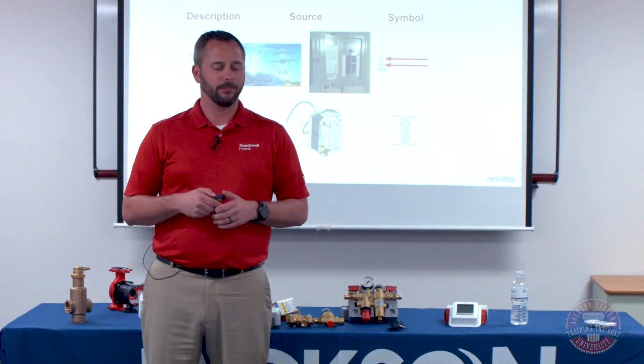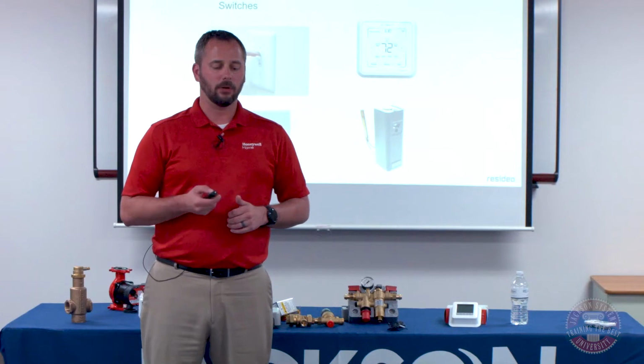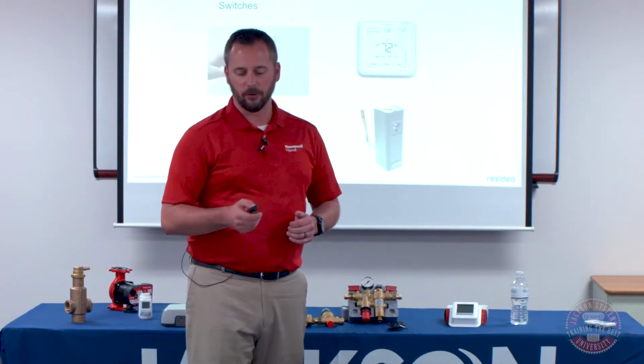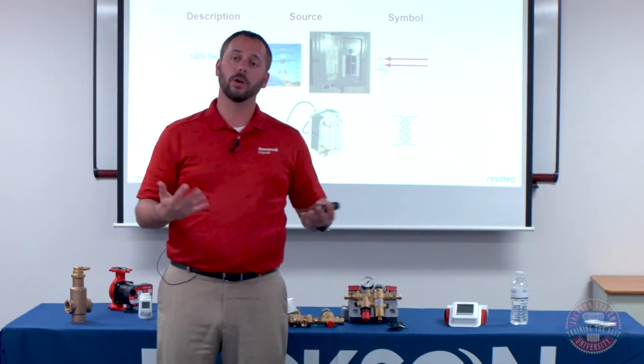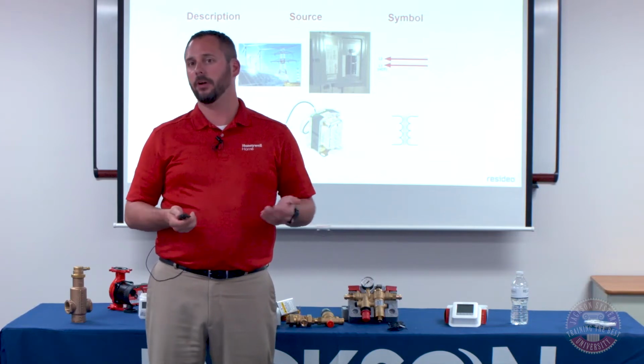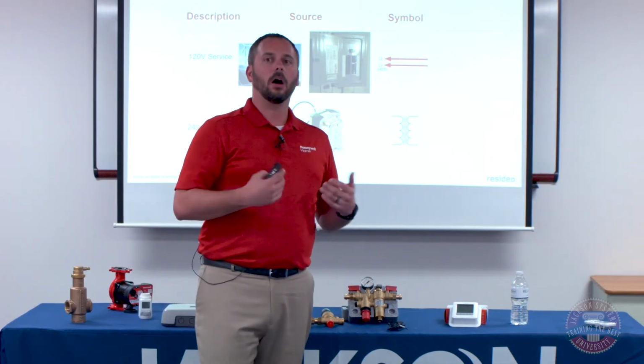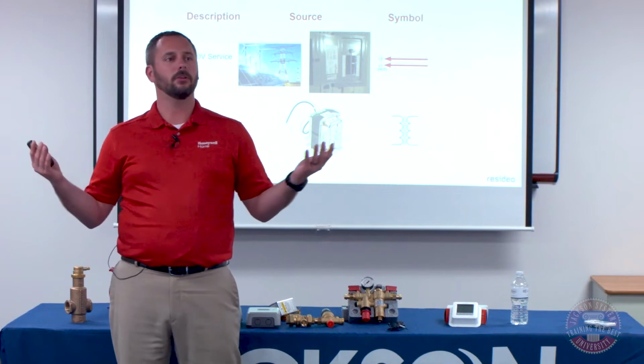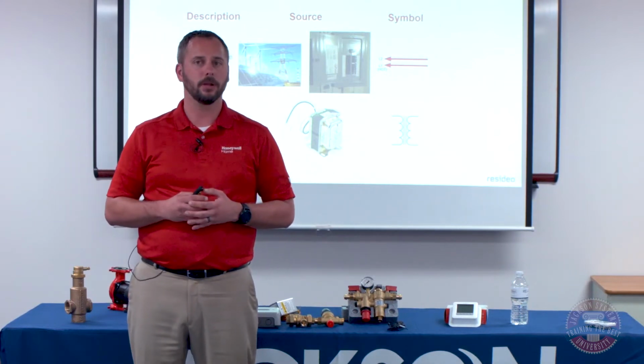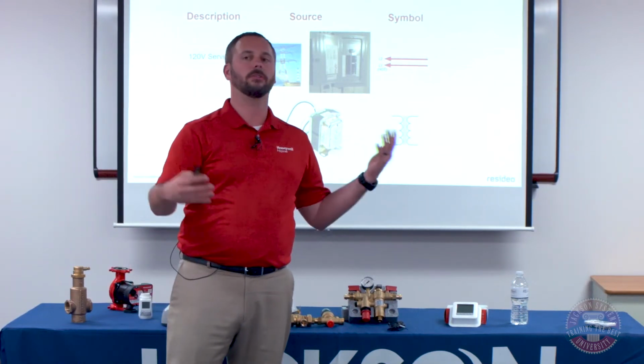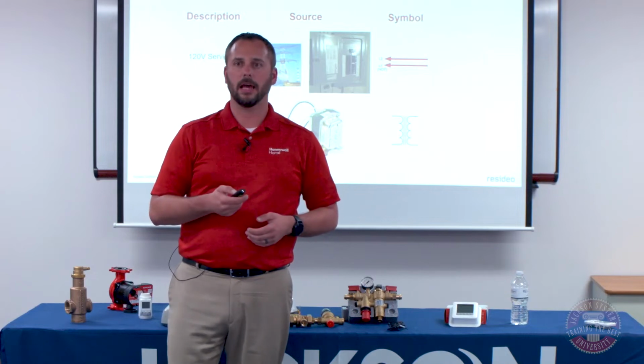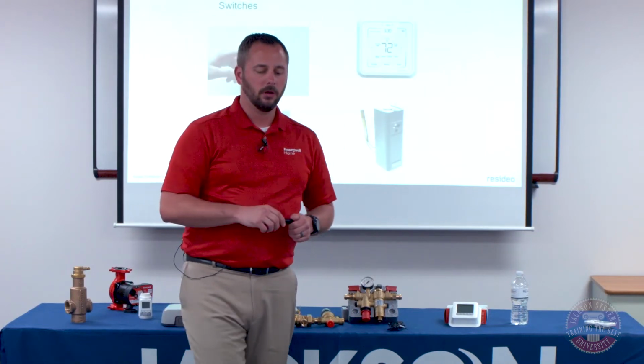In our world, I'm going to show you kind of how that relates. So when we're looking at power supplies, on the 24-volt side, it's typically a transformer. On the 120-volt side, that is usually power coming from your circuit breaker. And that could be 208 volt, etc. But this is kind of what we're looking at on our side for the power supplies.